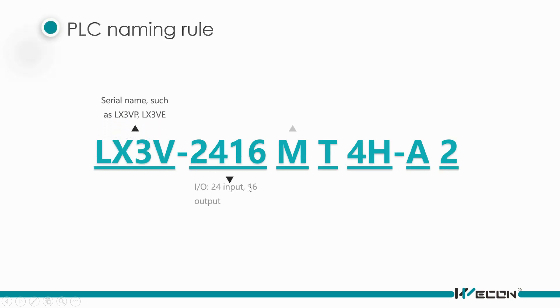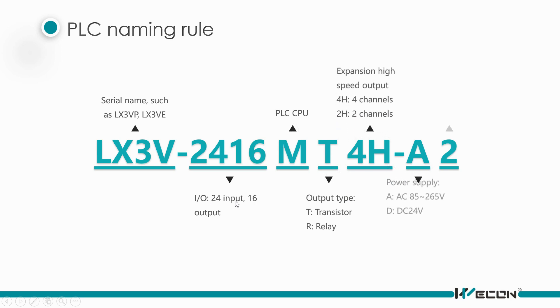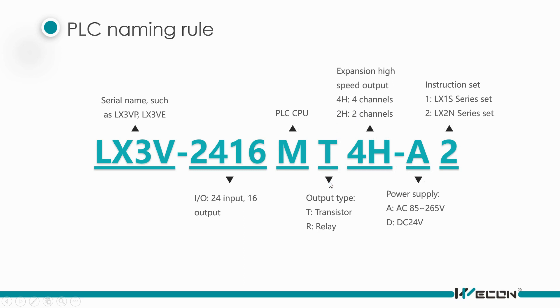Here is the naming convention of the PLC. '2416' means the I/O terminal number. 'MT' means transistor, 'R' means relay. '4H' means 4 channels of expansion high-speed output, '2H' means 2 channels. 'A' means AC power supply, 'D' means DC. The last number, '2', refers to the instruction set — generally we use the LX2N series instruction set.